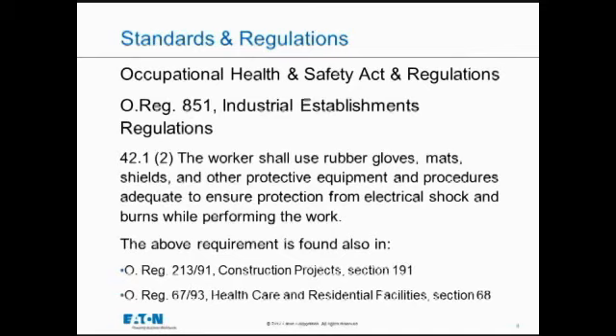Here in Ontario, we've got the Occupational Health and Safety Act and its regulations. And there are 3 regulations where this specific phrase 42.1 appears. It may not be the same number in construction and healthcare regulations, but in industrial establishments regulations, which would generally apply to this facility right here, if somebody was working on the electrical system and it's their workplace, then this would apply. The worker shall use the rubber gloves, mats, shields, and other protective equipment and procedures adequate to ensure protection from electrical shock and burns while performing the work.